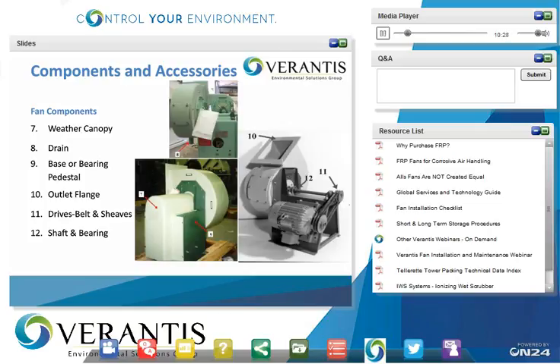Number seven is for arrangement 10. It is the one-piece weather canopy that's covering shaft, drive, and motor. Number eight is the drain. In our system, it is an option to select the drain. However, we strongly recommend everyone include a drain with the housing because it is easy for water to accumulate based on condensation, so the water will have no way to escape out if you don't have the drain with the housing.